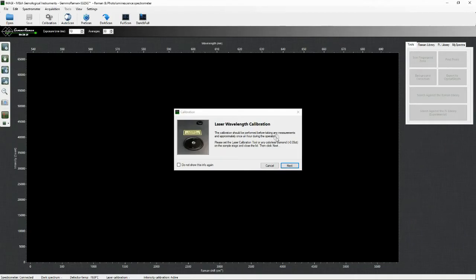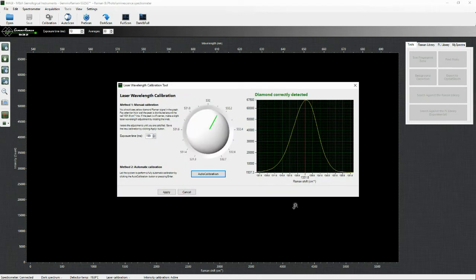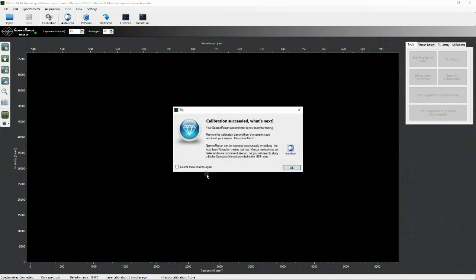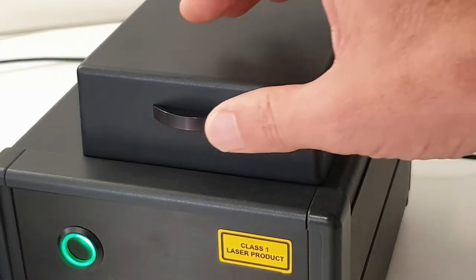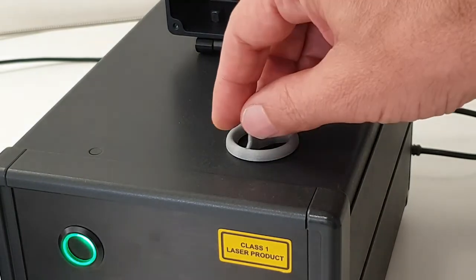A new window will now open with instructions on how to position a loose diamond if the calibration piece is not available. Click Next and a new window will open. On the right side you can see the magnified Raman signal of the diamond. A red line in the center should match the peak, which, if the unit is not calibrated, is usually a bit shifted. Press the auto calibration button. The software will now perform the procedure, and then the pop-up window will close automatically. Now the calibration piece can be removed, and the Raman is ready to scan.